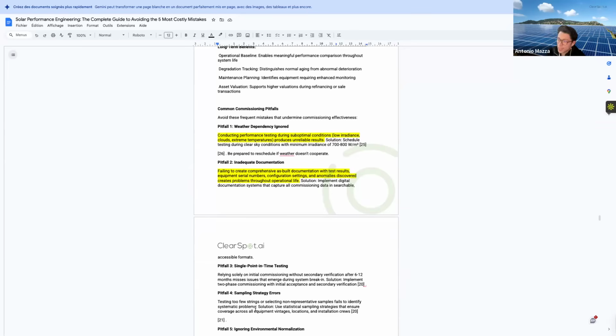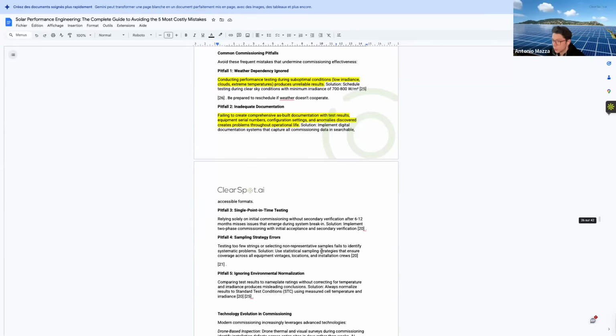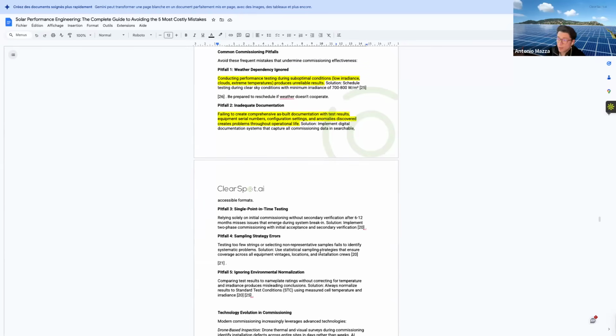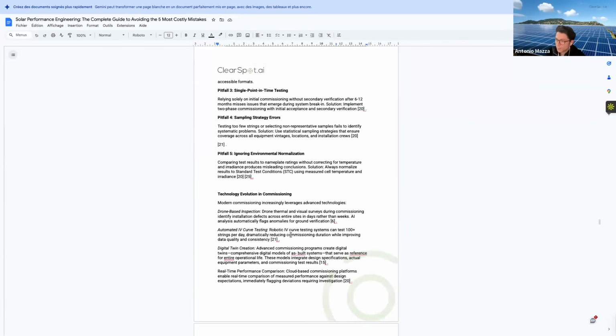Sampling strategy errors: testing too few strings, or selecting a non-representative sample, fails to identify a systematic problem. Solution: use statistical sampling strategies that ensure coverage across all equipment vintage, location, and installation crews. Ignoring environmental normalization: comparing test results to nameplate rating without correcting for temperature and irradiance produces misleading conclusions. Solution: always normalize results to standard test conditions using measured cell temperatures and irradiance.